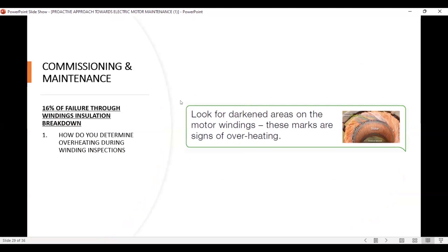So how do you determine that your motor is overheating? Normally, when motors are overheating, you will see dark spots on the winding. So when you are replacing your motor bearings, or doing any replacement on your motor, take advantage to check the windings. Dark spots are signs that your motor is undergoing overheating, so that corrective action is put in place. Next slide.